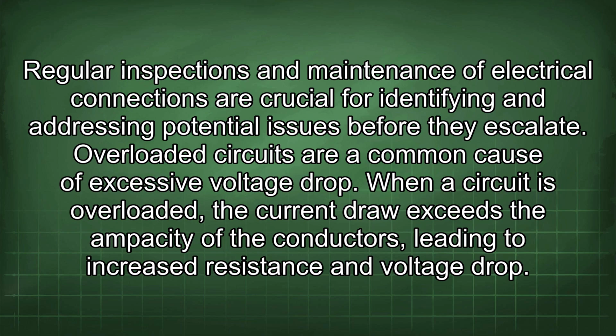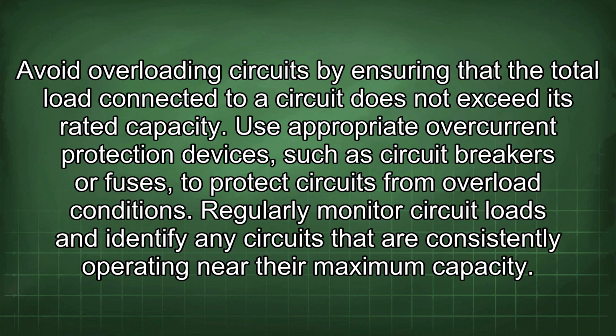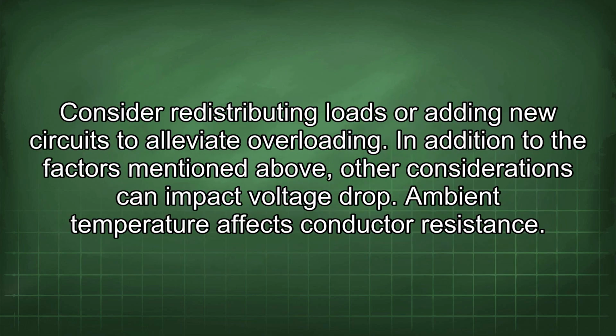Overloaded circuits are a common cause of excessive voltage drop. When a circuit is overloaded, the current draw exceeds the ampacity of the conductors, leading to increased resistance and voltage drop. Avoid overloading circuits by ensuring that the total load connected to a circuit does not exceed its rated capacity. Use appropriate overcurrent protection devices, such as circuit breakers or fuses, to protect circuits from overload conditions. Regularly monitor circuit loads and identify any circuits that are consistently operating near their maximum capacity. Consider redistributing loads or adding new circuits to alleviate overloading.